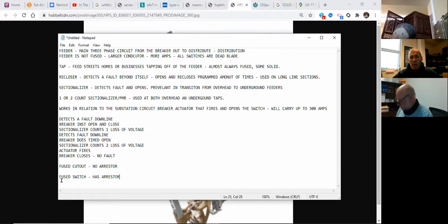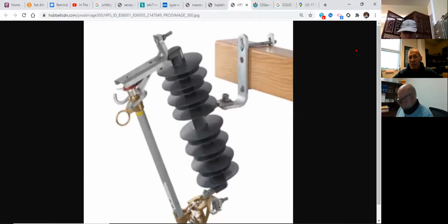All right, so for a fuse switch, all you've got to do on this picture is add the lightning arrestor to it, and then you're good to go. Now, as far as a fuse cutout and a fuse switch, you're going to use these at different locations. For transformers and anything you need to arrest lightning at, you want to keep that as close to the location as possible, so we're going to use a fused switch with a lightning arrestor installed on it.